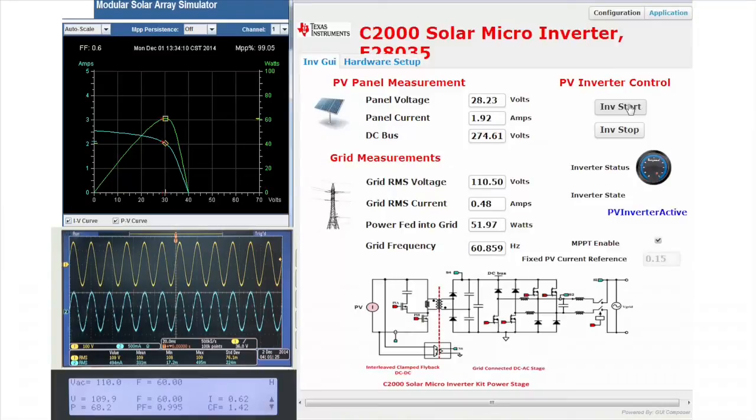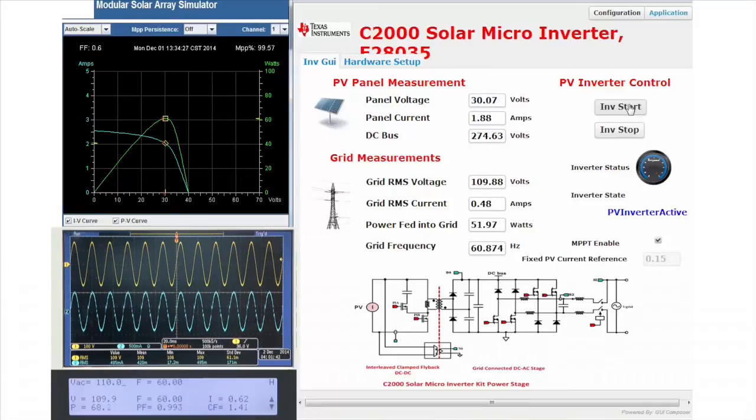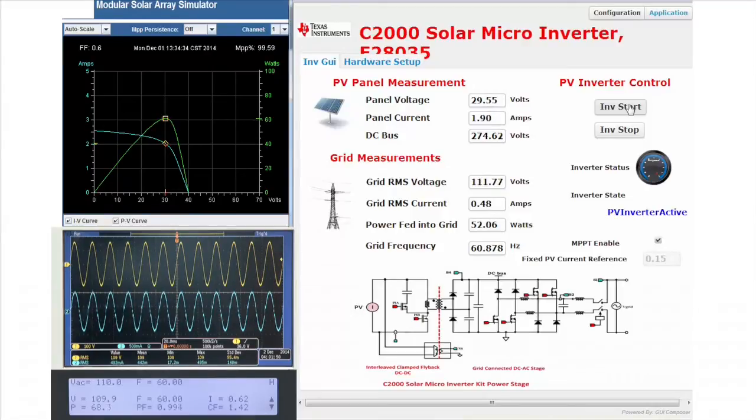In this test, the PV panel emulator characteristics are fixed and hence the tracking efficiency is called static MPPT efficiency. We see the DC bus is being regulated properly. On the oscilloscope, we can see the steady state waveform of the grid voltage and current. We see a clean current waveform that is in phase with the grid which shows good control of the grid current.